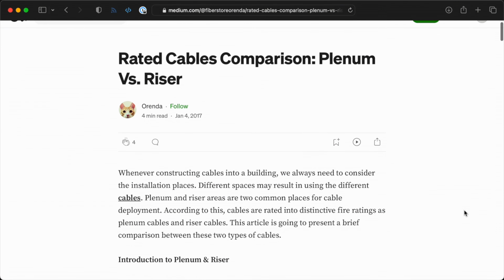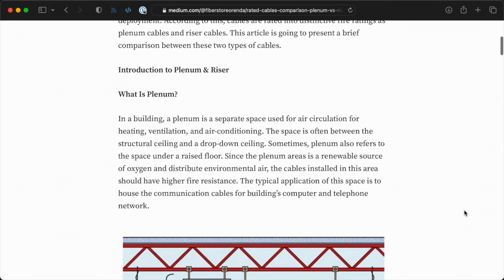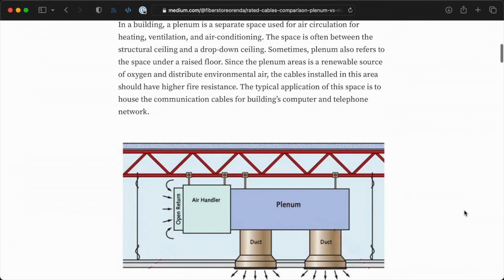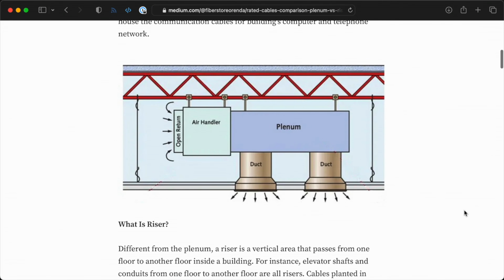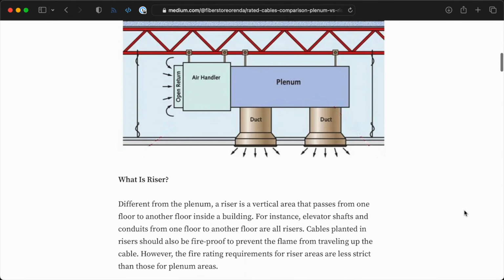This video is not diving that deep, but at least for my office or something like it, you should know the difference between plenum and riser cable when you buy in bulk for an install. Plenum cable goes in plenum spaces, and riser cable goes most everywhere else. What's a plenum? It's that area up above the ceiling tiles. In many commercial buildings, the space above the drop ceiling is used as a giant return air duct for the space. That airflow delivers tons of fresh oxygen.